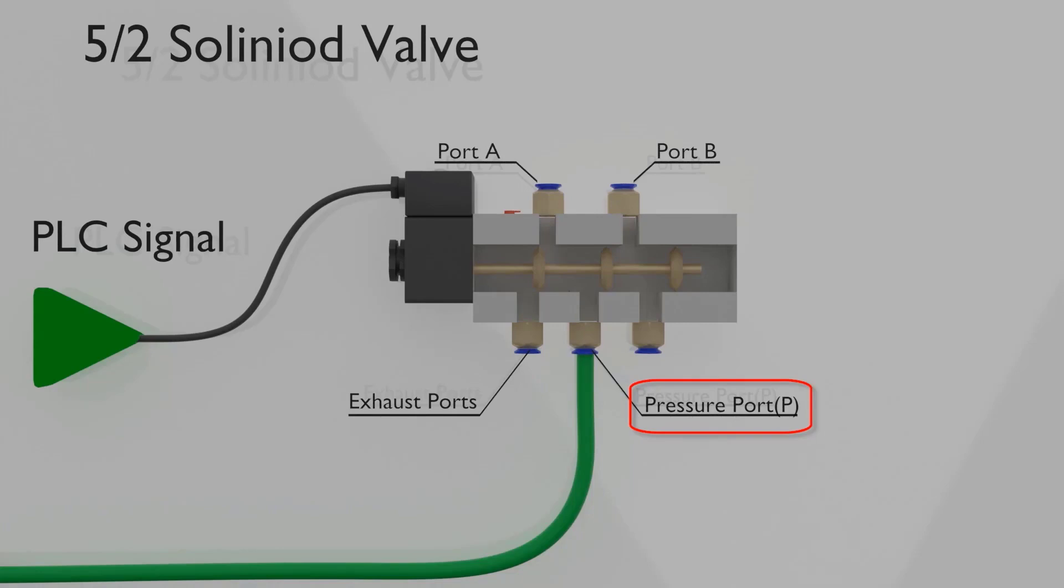The pressure port P is linked with either port A or port B when the spool inside the valve moves. So when port P is linked with port A, the spool blocks the entry of the air towards port B. Similarly, when port P is linked with port B, the spool blocks the entry of the air towards port A.